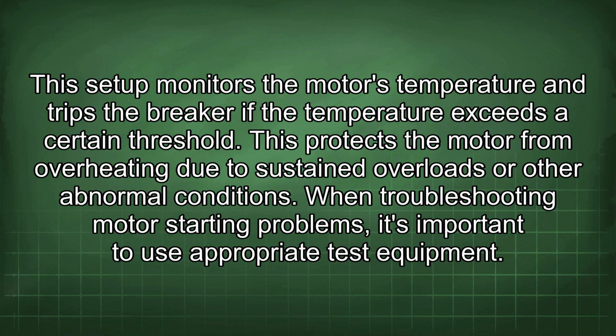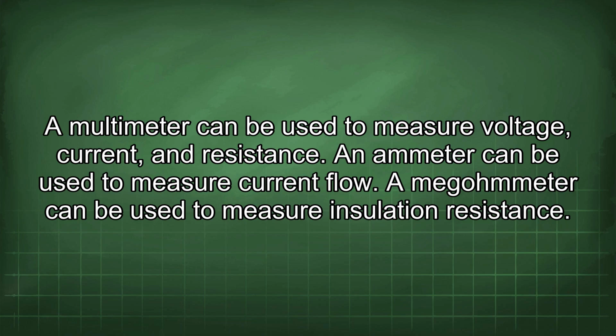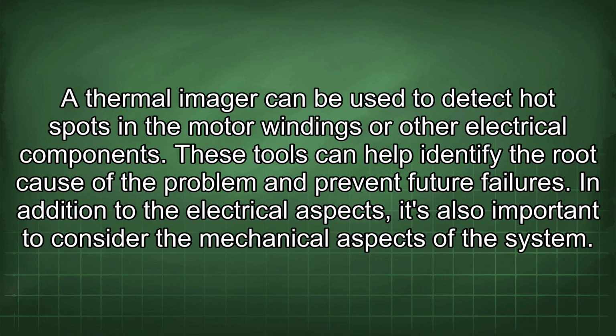When troubleshooting motor starting problems, it's important to use appropriate test equipment. A multimeter can be used to measure voltage, current, and resistance. An ammeter can be used to measure current flow. A megohmmeter can be used to measure insulation resistance. A thermal imager can be used to detect hot spots in the motor windings or other electrical components. These tools can help identify the root cause of the problem and prevent future failures.